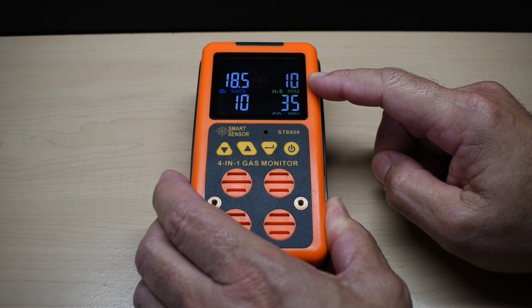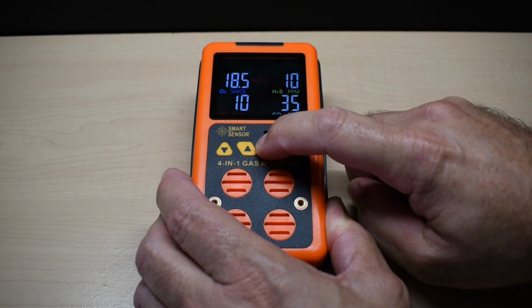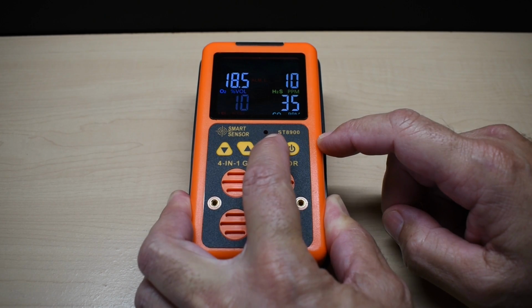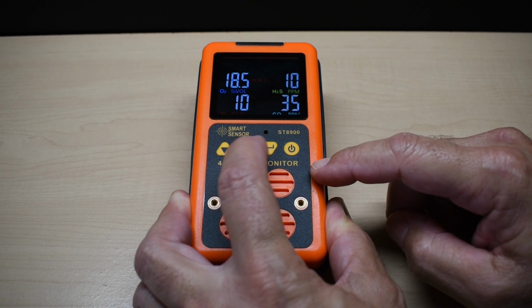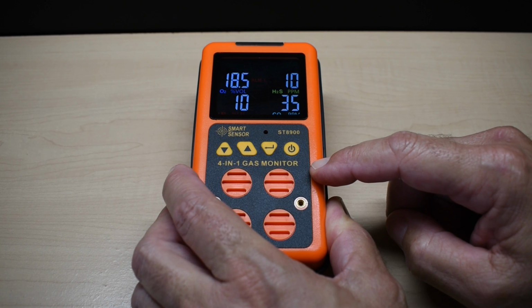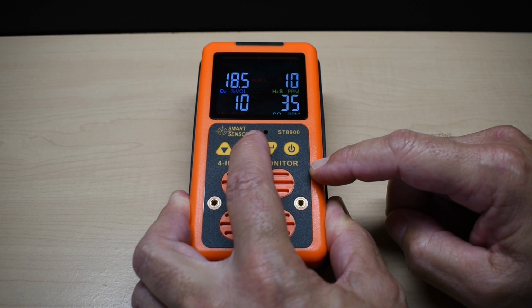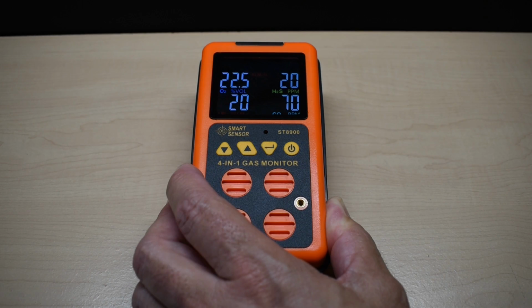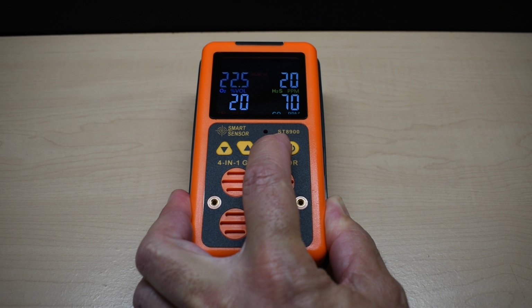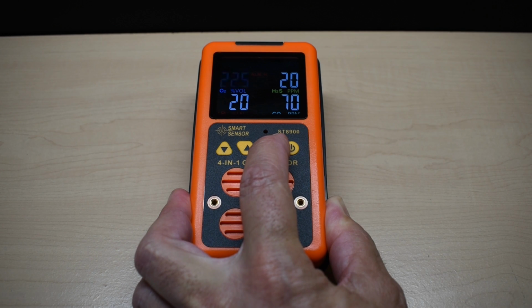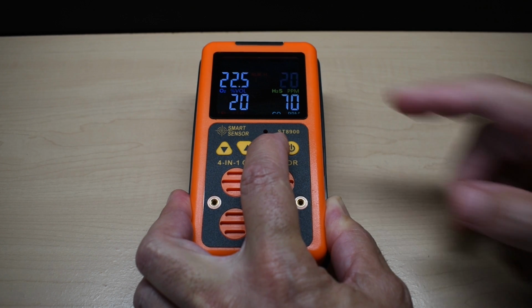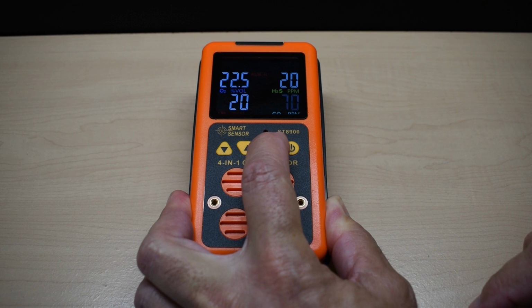Hydrogen sulfide, a different value, I can change it right here. And over here I could do the carbon monoxide. Once that's done, I can push this again. Now you can see the settings could be adjusted at the high end. You would simply push enter. If you don't want to do anything with it, just skip it. Now you're here, go to each one, change the values, and you're good to go.